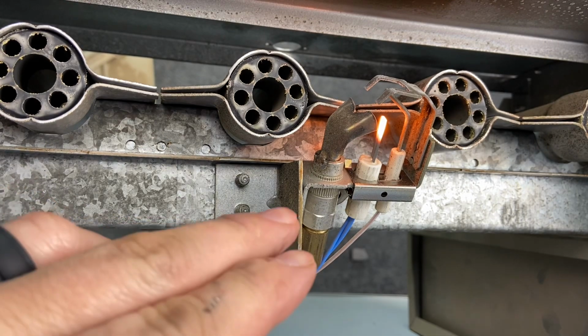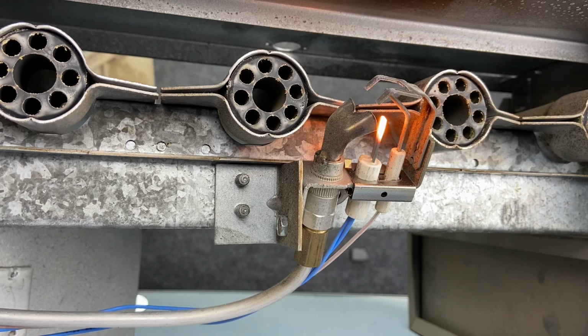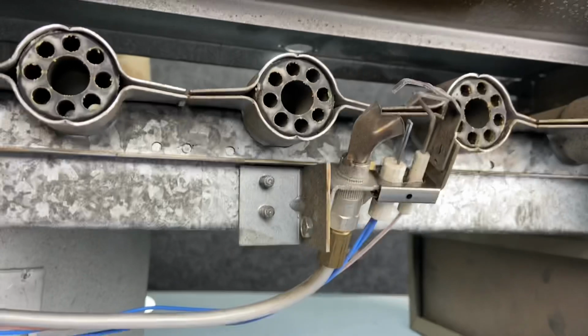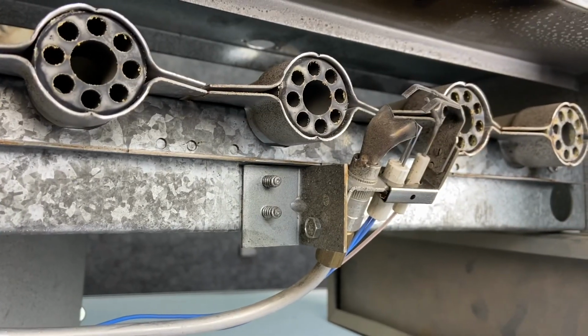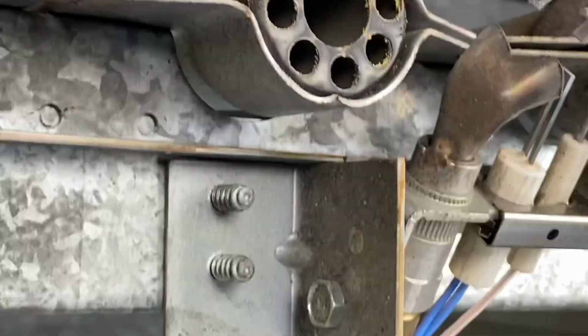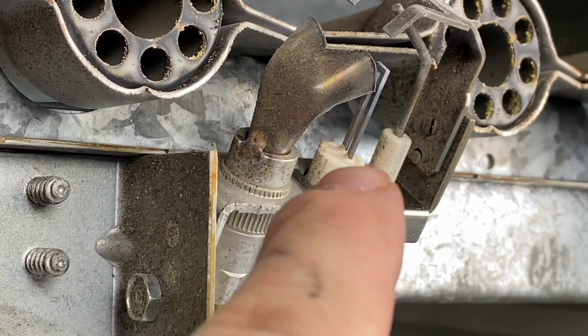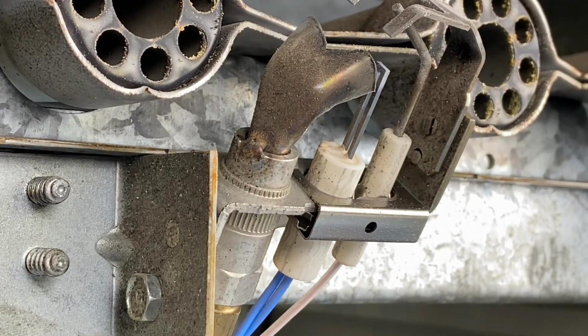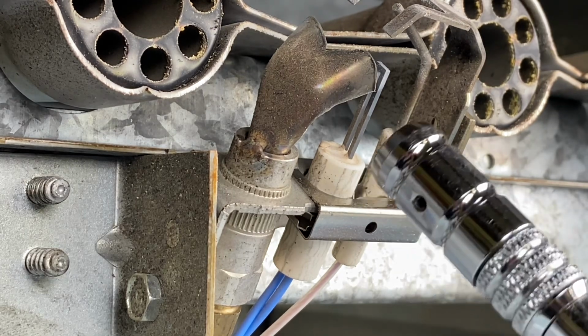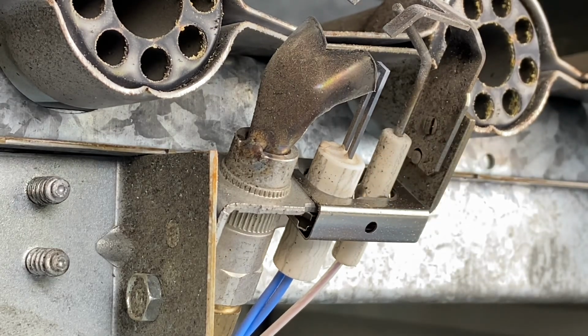Now these are very fragile. If you look at these wrong, they break. So you've got to be very, very careful if you're working on this type of furnace. This little hot surface igniter is extremely sensitive, so I make it a point to not touch them, to not really mess with them. So these hot surface igniters right here are really, really fragile. I make it a point to not touch them because any little bit of pressure you put on there, that little bitty resistive material breaks so easily.